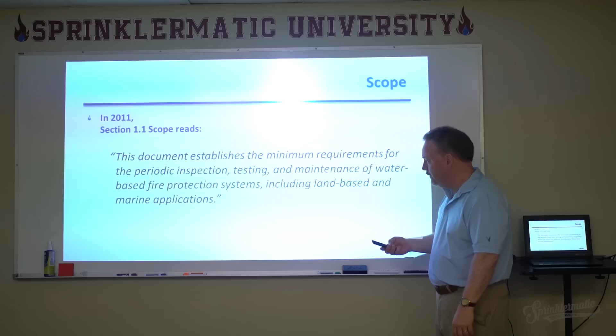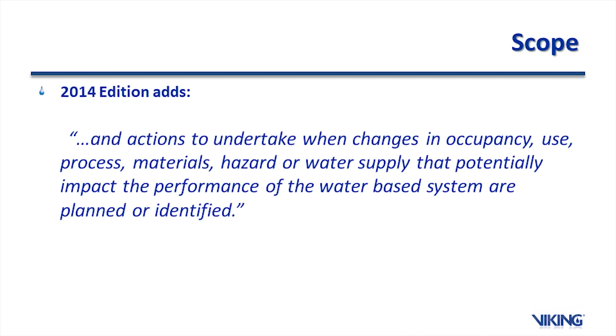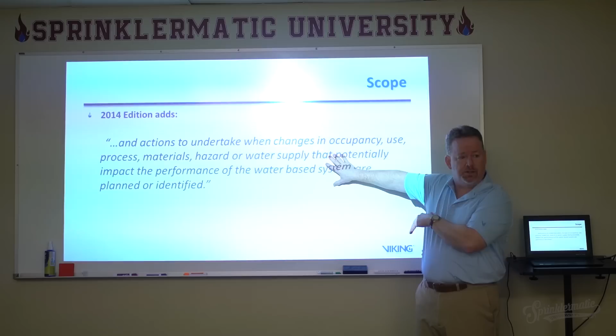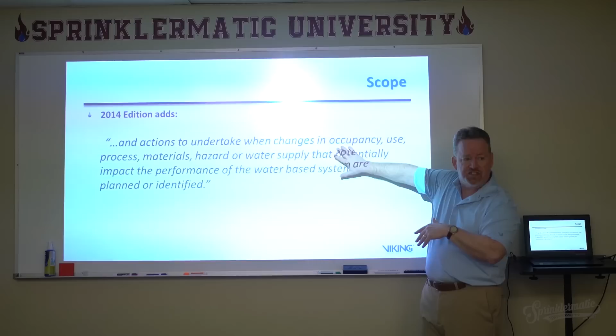But in 2014, they added this: actions to undertake when changes in occupancy, use, process, materials, hazard, or water supply that potentially impact the performance of the water-based system are planned or identified. So the first question was, why did it change? Well, it changed because this is in fact a true statement—NFPA 25 does include these requirements within the responsibilities of the owner. They added it just to clarify the scope and clarify that the committee's work did include this type of requirement.